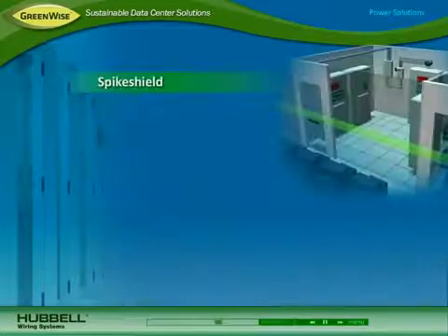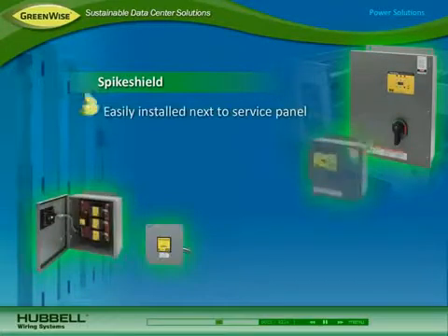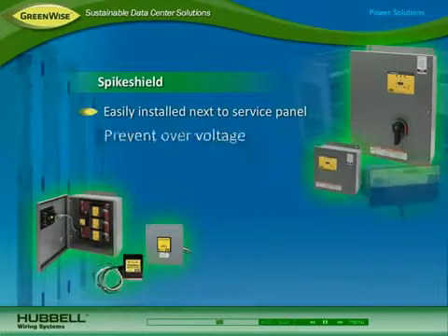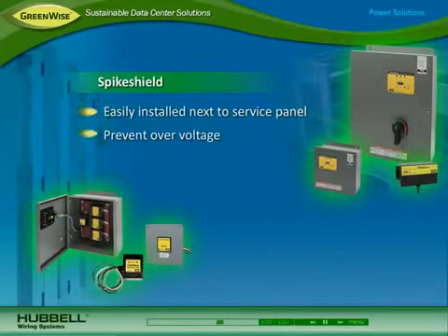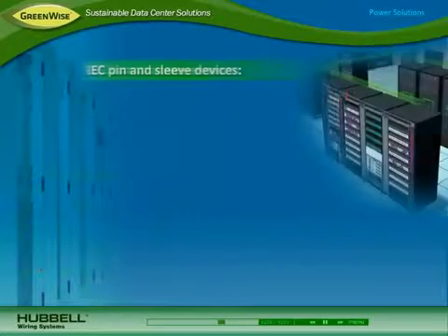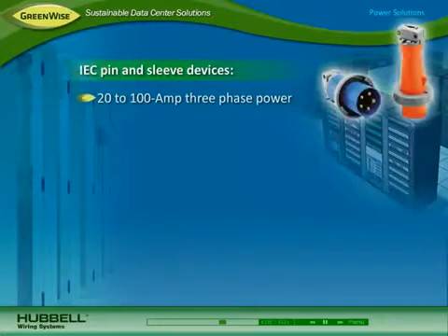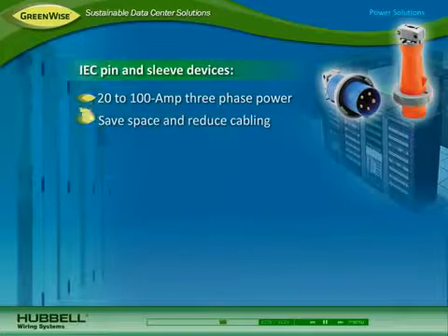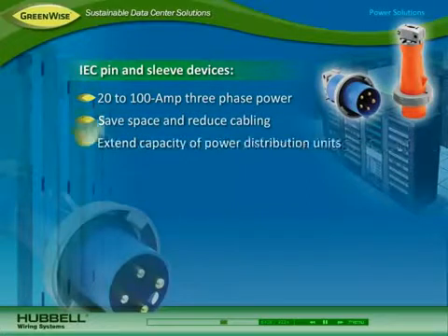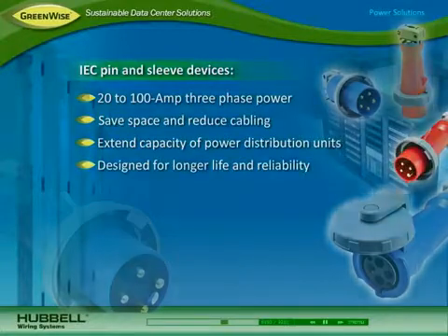In the utility room, Hubbell Spikeshield service entrance and branch surge protection devices are easily installed next to the incoming service panel, prevent over-voltage that can impact critical network equipment and cooling systems, and they handle a peak amperage capacity of 40 kA to 320 kA. By delivering three-phase power to cabinets, Hubbell IEC pin-and-sleeve 20-amp to 100-amp power receptacles save space and reduce cabling for better airflow, extend the capacity of power distribution units, and they're designed for longer life with reliable contacts.